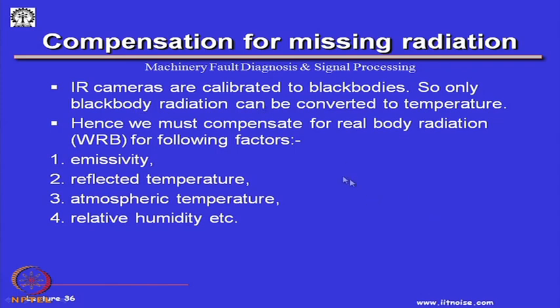Now, these IR cameras are calibrated to black bodies. So, only black body radiation can be converted to temperature. Hence, we must compensate for real body radiation, the most important being emissivity, reflected temperature, relative humidity, and atmospheric temperature, because these factors will affect the infrared waves emitted from a body. But most importantly, let us look into this emissivity.